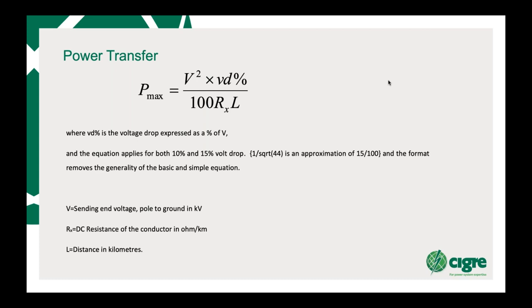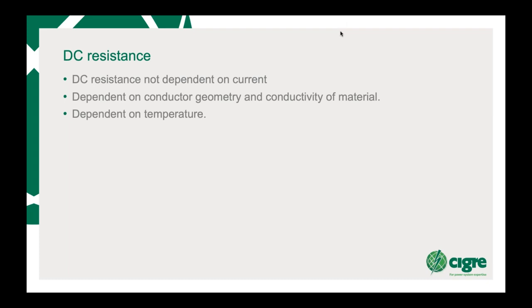So you haven't got the same interaction on a DC line as you've got on an AC line in relation to surge impedance loading and things like that, which gives your DC options now quite a bit more variation. In addition, which we'll get to, DC resistance is not dependent on current because you haven't got this transformer effect. So what it really is dependent on is your conductor geometry, conductivity of material, and temperature. So really, to get the resistance lower for a DC line, what you need to do is put a bigger conductor up. It doesn't matter what the core is, as long as you've got a lot of aluminium or low resistance material, that will give you higher power flow and lower resistance.